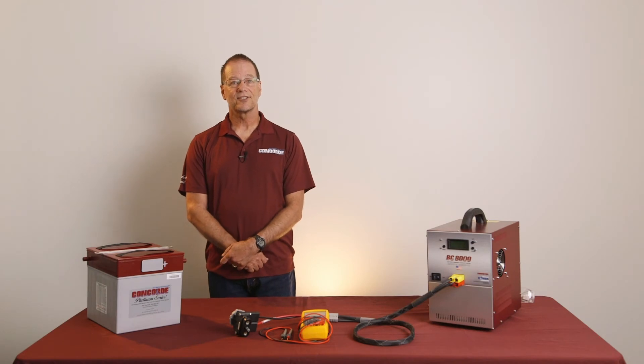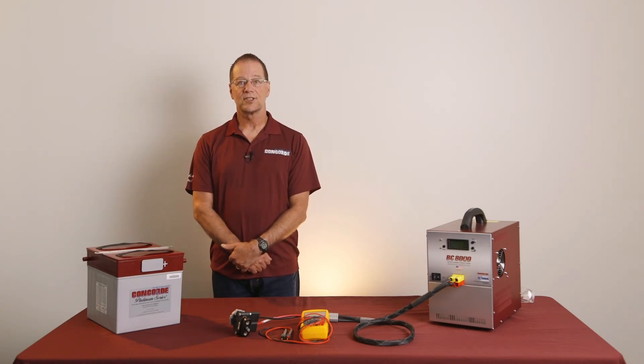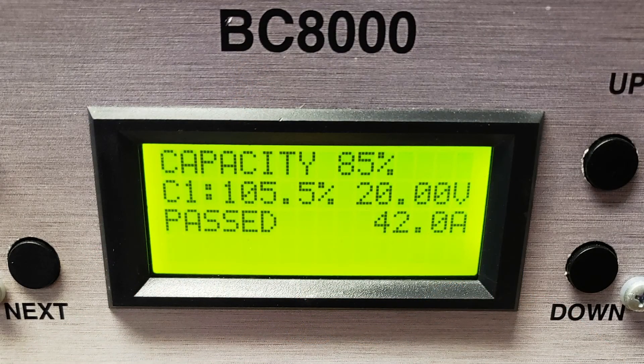The capacity test is finished. On the screen are the readouts from the BC8000 to show you the results. The battery we tested gave 105.5% capacity at the 42-amp rate, which is definitely a pass. The minimum to pass is 85%, or 51 minutes at the C1 rate. In the CMM, there is a formula to convert runtime minutes to capacity percentage. If the battery had tested below 85% or 51 minutes, then it would have failed the capacity test. If this happens, you would need to proceed with a conditioning charge and repeat the capacity test. The conditioning charge procedure will be covered in a separate training video.